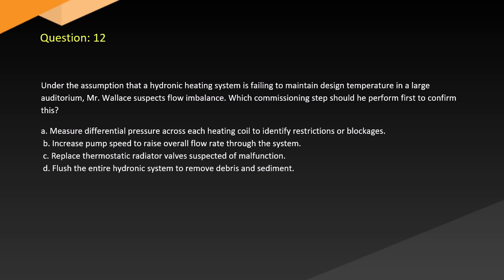Question 12. Under the assumption that a hydronic heating system is failing to maintain design temperature in a large auditorium, Mr. Wallace suspects flow imbalance. Which commissioning step should he perform first to confirm this? A. Measure differential pressure across each heating coil to identify restrictions or blockages. B. Increase pump speed to raise overall flow rate through the system. C. Replace thermostatic radiator valve suspected of malfunction. D. Flush the entire hydronic system to remove debris and sediment.